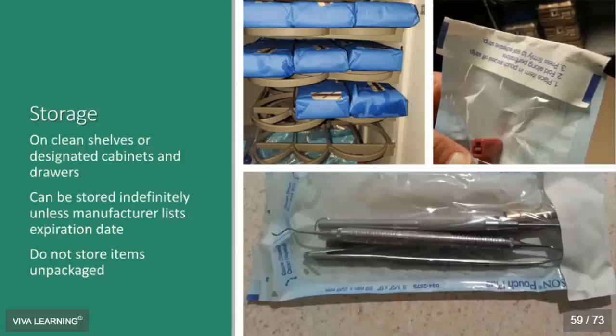So a common question I get is, how long can I store these instruments before I have to reprocess them? Well, you can store them indefinitely because it's event related, right? As long as the integrity of the packaging is in place, you do not have to reprocess those, unless the manufacturer lists an expiration date. So you do want to check the manufacturer's expiration date for the package.